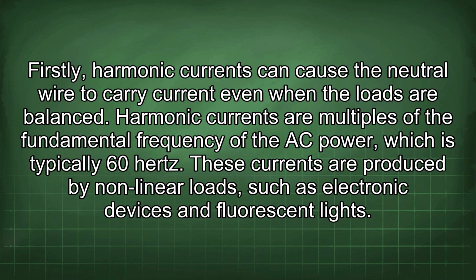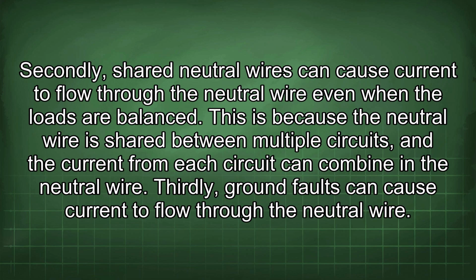These currents are produced by nonlinear loads, such as electronic devices and fluorescent lights. Secondly, shared neutral wires can cause current to flow through the neutral wire even when the loads are balanced. This is because the neutral wire is shared between multiple circuits, and the current from each circuit can combine in the neutral wire. Thirdly, ground faults can cause current to flow through the neutral wire.